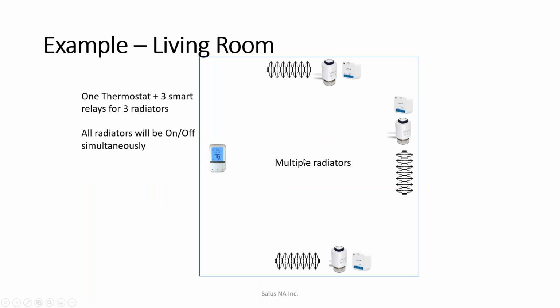A living room, you can have this one thermostat control multiple radiators. We have 3 radiators in the space, and each one of them has the relay kit with the actuator. And all radiators will be turned on and off simultaneously in this design, because they're all being controlled by that one thermostat.